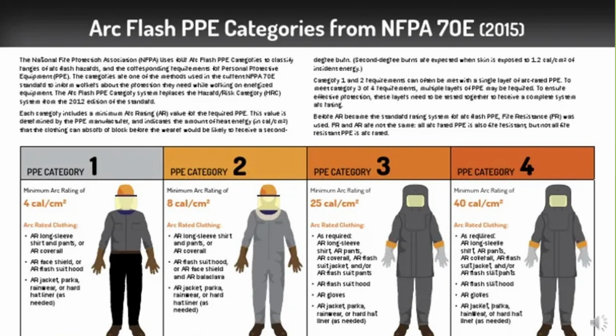So category 2, this is typically where you're going to fall if you're breaking into a live duct run, if you're on a duct run crew, where you're chipping concrete. Again, we'll know the voltages ahead of time, and we'll have a safety stand-down before any of that work commences to make sure that you have all the protection that you need. But it's always important to ask the question, like, hey, do I have everything I need to wear to perform this work? The only real addition for category 2 is the balaclava that will be underneath your face shield to protect the skin of your neck and your face. Again, this will be thoroughly gone over before any of that work commences.